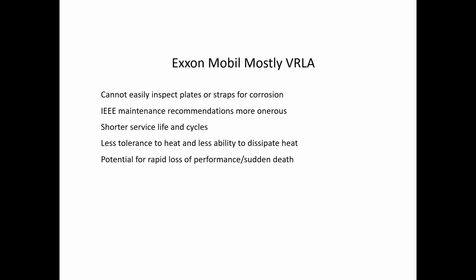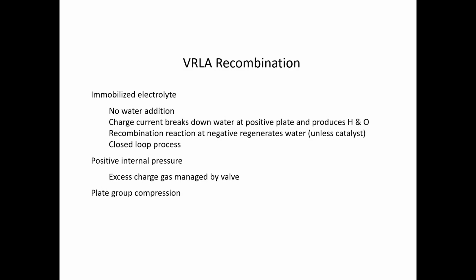These valve-regulated batteries, it's a much more linear loss of capacity, and like I said, some of the failure modes can lead to a rather quick loss of capacity. So you really have to stay on top of these batteries for maintenance, so you're not unexpectedly surprised by a dead battery. Shorter service life and cycles. They are less tolerant to heat because they are in steel cans and they're typically stacked on top of each other. Their ability for convection cooling is not as good as it is in a flooded battery. Flooded battery, you have that free floating electrolyte. They're open rack design, so they're much more tolerant to heat. They can dissipate heat a lot easier. And then I mentioned before the potential for rapid capacity loss is important to think about.